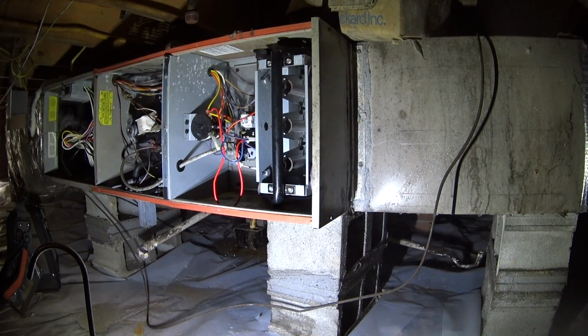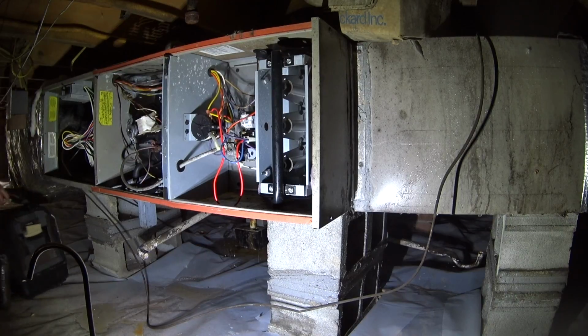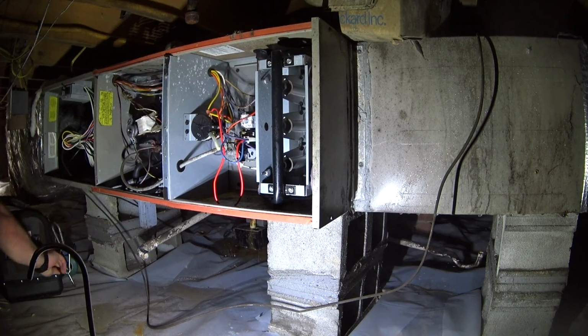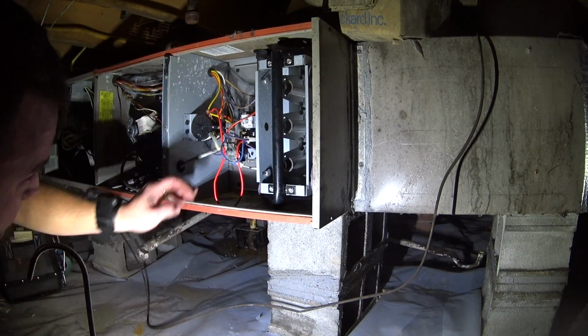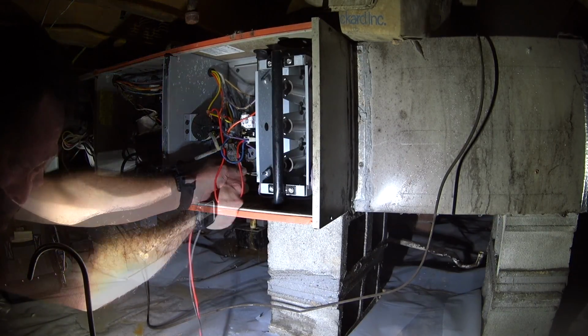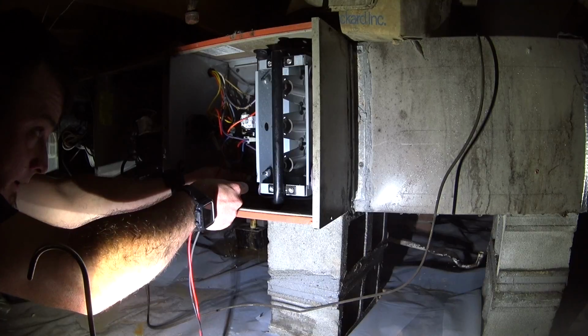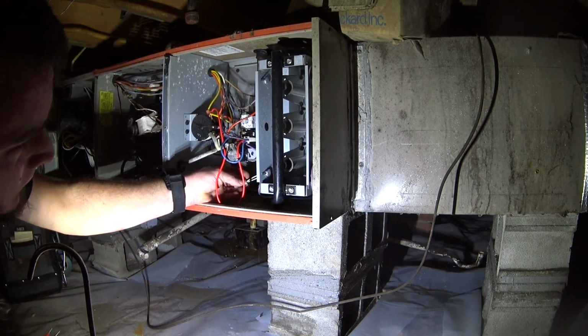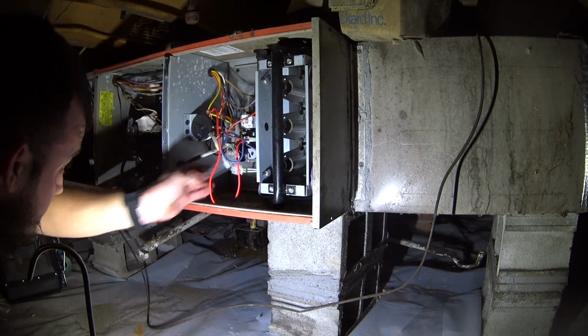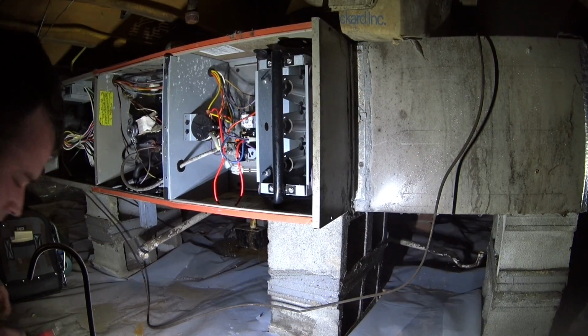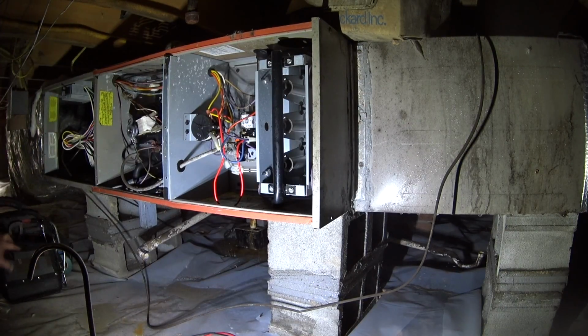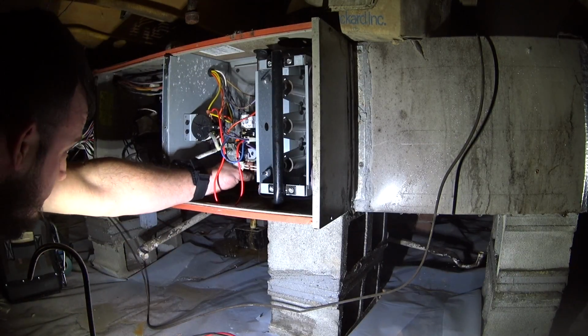Let's see what the igniter looks like. We're gonna ohm out the igniter. 94.9. If I recall correctly, that's actually not an obscene resistance value for that particular igniter type.